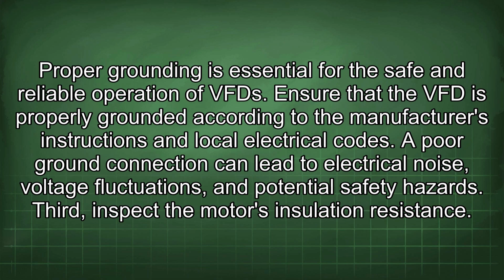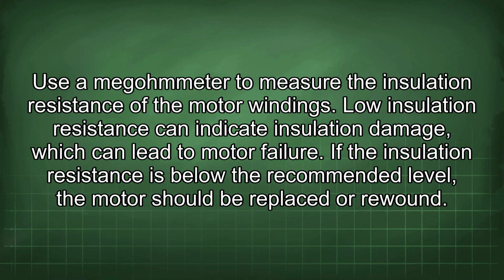Third, inspect the motor's insulation resistance. Use a megohmmeter to measure the insulation resistance of the motor windings. Low insulation resistance can indicate insulation damage, which can lead to motor failure. If the insulation resistance is below the recommended level, the motor should be replaced or rewound.